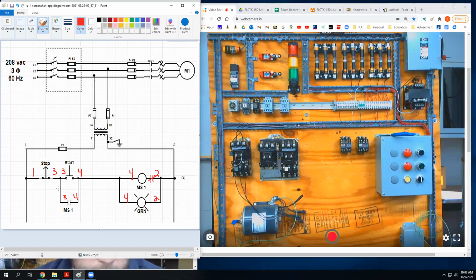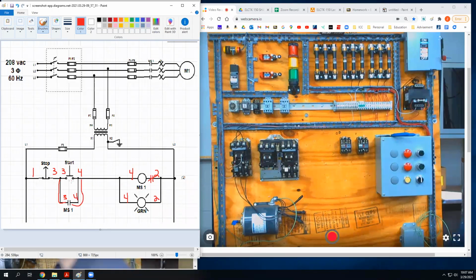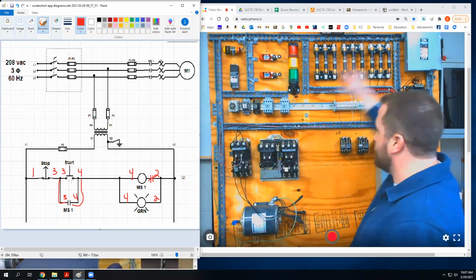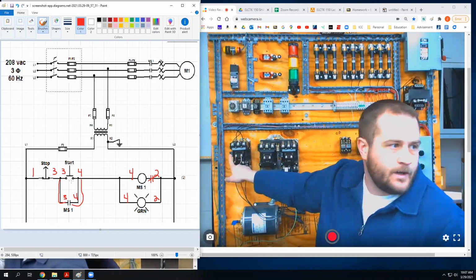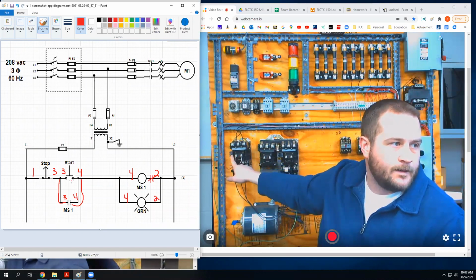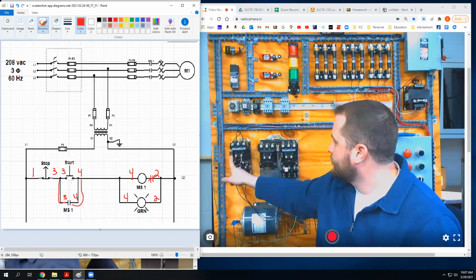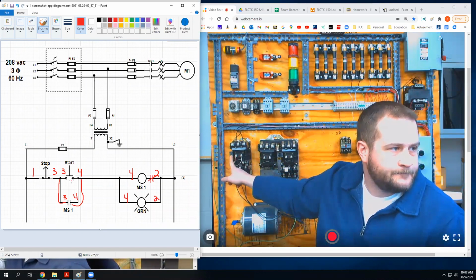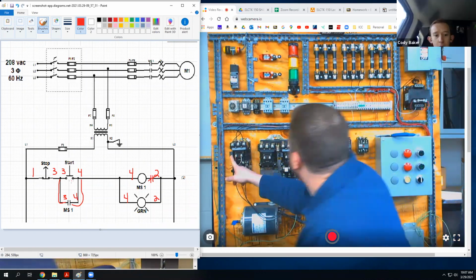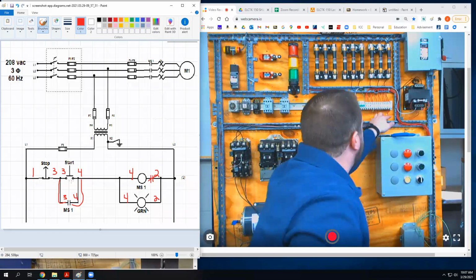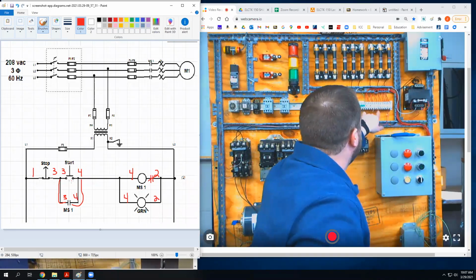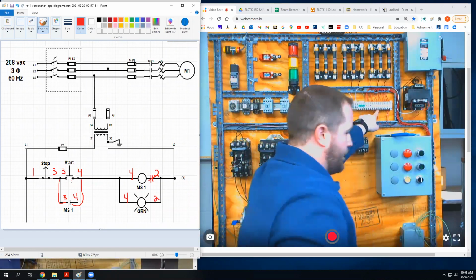So basically all I need to do is add this wire and this wire. On this auxiliary contact, which on mine is right here, make sure my disconnect's off. I need a number 3 to go here on one side, and a 4 on the other side. So where's my closest number 3 wire? Anybody remember? We up at the push button. Right, basically my only number 3 is right here, and it goes from here to this little jumper. So the closest one is going to be right here.